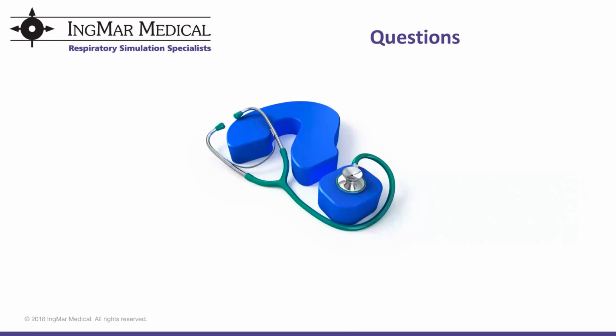Evan asks, what does being an ISO 17025 accredited lab really mean to us, the customer? Hello, Evan. Having an ISO 17025 accredited lab simply means that our numbers are audited yearly by a third party. IngMar Medical could issue a calibration certificate and issue that to the customer. But to know that those numbers are correct, there's oversight in the 17025 accreditation bodies. So ISO says, say what you do, do what you say. If we say our numbers are correct, so does a third party accreditation body. So that is what it means to you. It's not just us saying it, it's actually IngMar Medical and A2LA saying it.